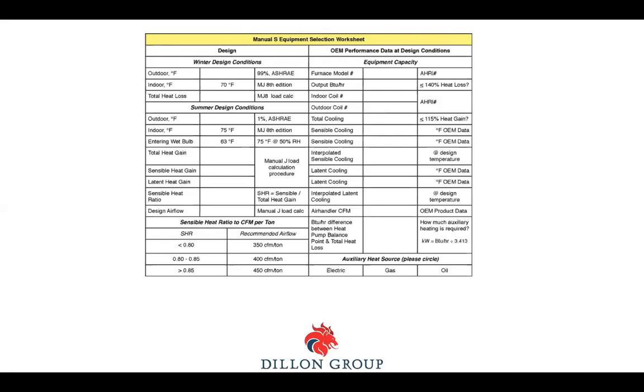So this problem down in Corpus, found out that all the indoor units, the air handlers, are 2.5 ton air handlers. The outdoor units might be a 1.5 ton outdoor coil, or it might be a 2 ton outdoor coil, depending on the size of the apartment. How big is the square footage? There was no Manual S done. The manufacturer came out and said there's too much airflow going through the system, so we need to damper it down. The way they described it, they didn't use dampers. They said we inserted some blocks to reduce the amount of airflow going through the system so that it would spend more time on the coil to dehumidify.